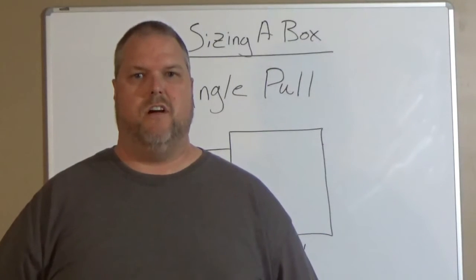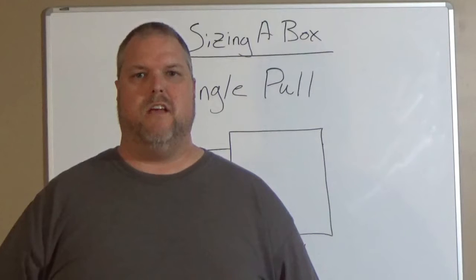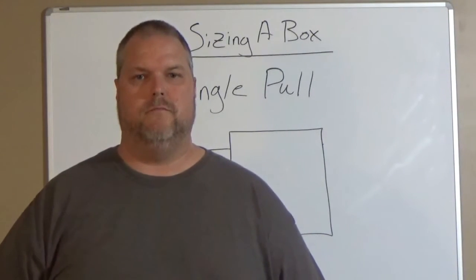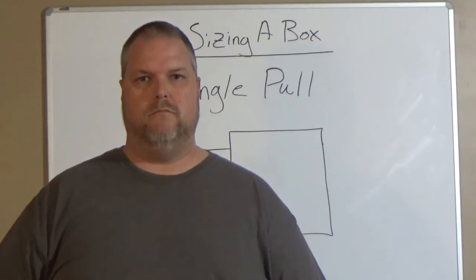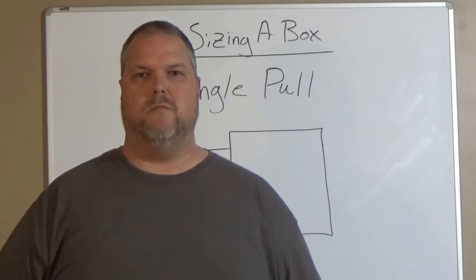Today we're going to discuss how to size a junction box for an angle pull. In the last video we did the straight pull. Straight pull, remember, is multiplied by 8.